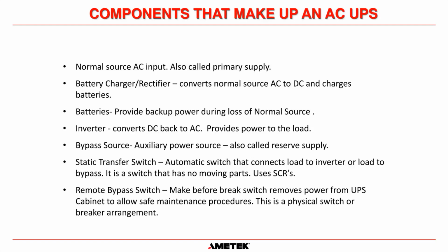The batteries obviously provide backup power during a loss of normal source power. The inverter converts the DC back to AC and provides power to the critical loads that are being backed up by the UPS itself. The bypass source, which is also called auxiliary power source, or maybe even the reserve supply, is a backup supply of AC power that we use if everything in the UPS itself has failed. We want to have another source of power for redundancy or to do maintenance if possible.